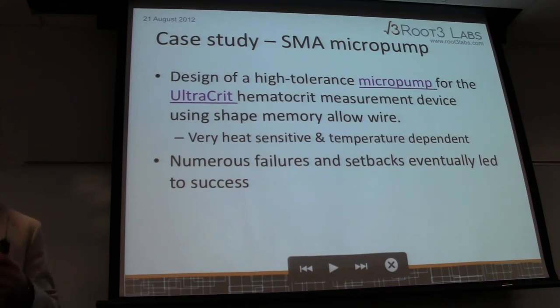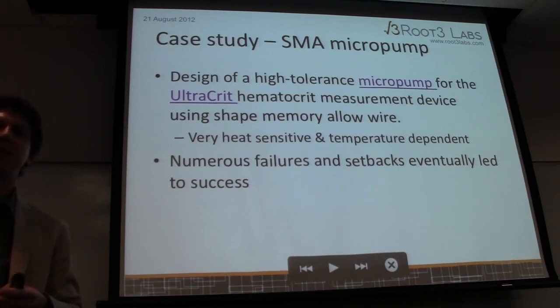So we were really going with the rapid prototyping, SLA and cast urethane, and we were having some inconsistent data, some intermittent failures, and we were starting to see that the thermal instability of these materials was causing problems. One lesson that we didn't learn quite in time was that I would recommend that at some point you look towards production techniques, if you're going to put the design through its paces. So you want to really understand what it is that you're working with before you start to do environmental testing and things like that.